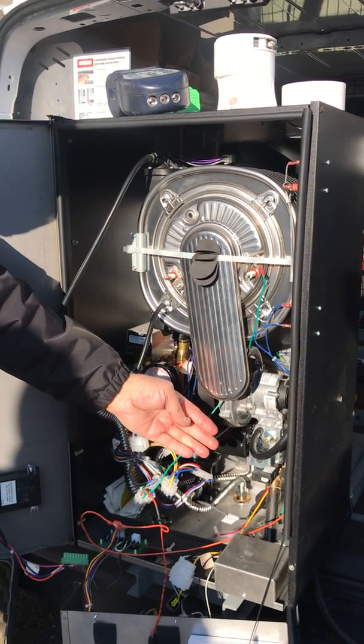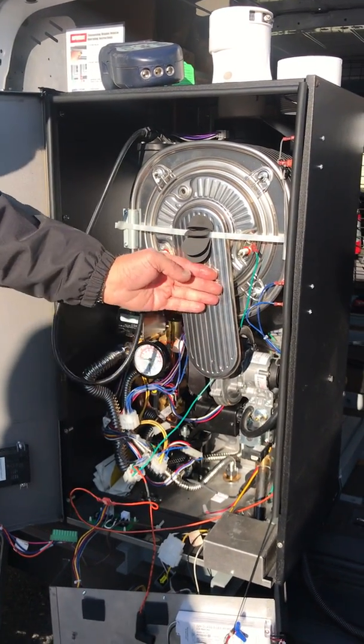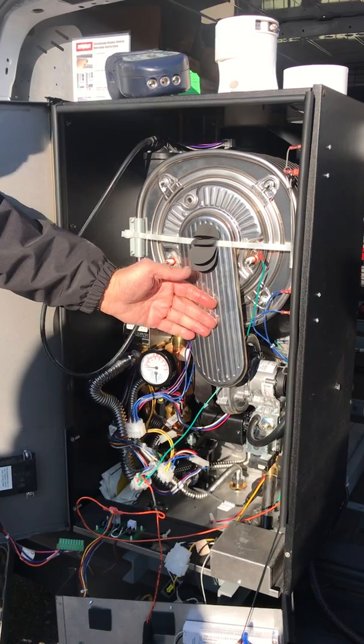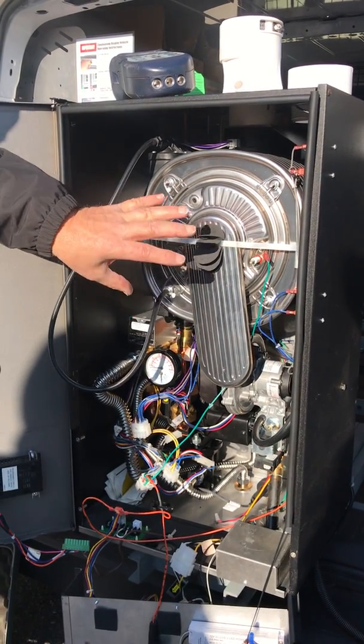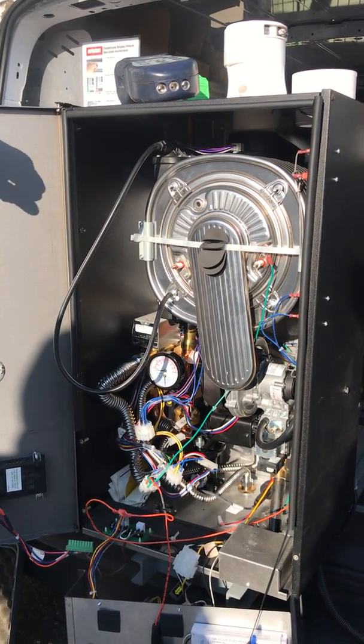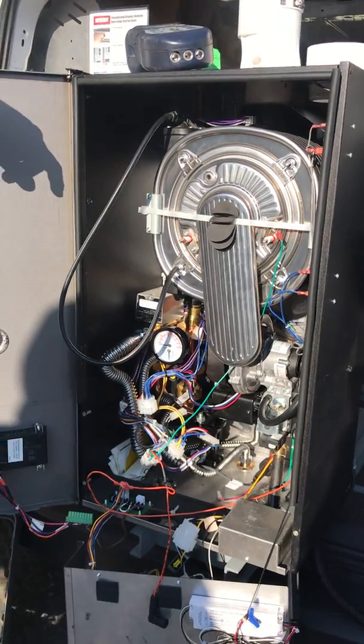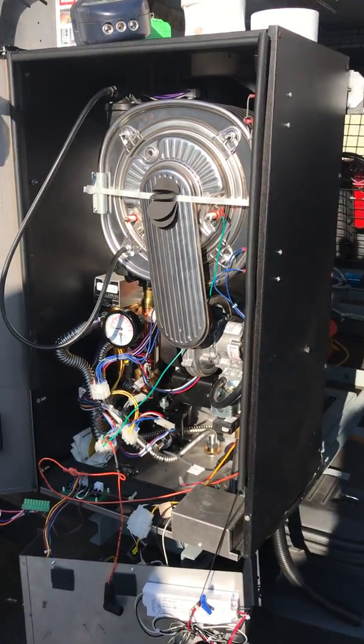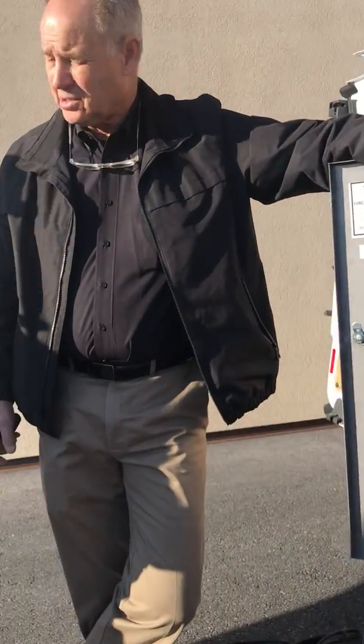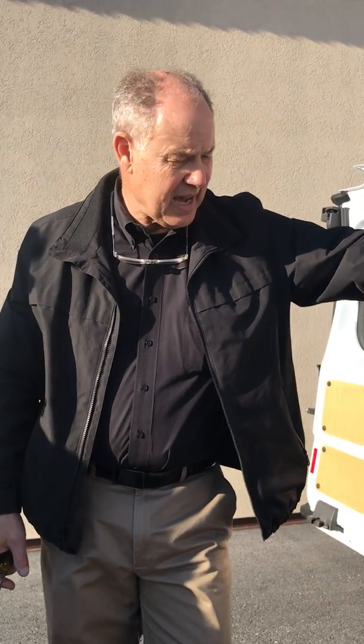So the cool air comes in and it mixes with the gas. And we actually have a gas-air mixture that goes through the center of the burner. But I would actually pull that just to take a look at it. I would check my flame signal and see what that is.